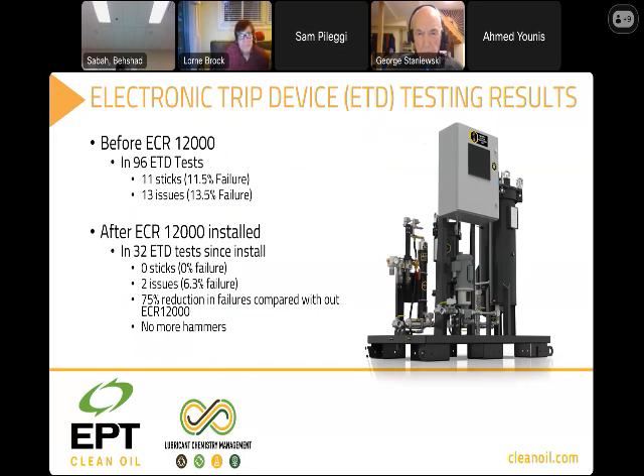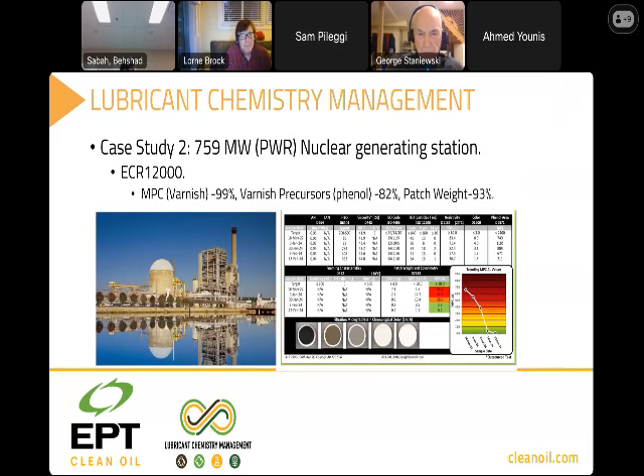The valve in 96 tests, they had about a 13% failure rate before. And after we put the system on, it went down to 6.3%. So pretty remarkable. Now, we don't see these results in the nuclear application because nuclear starting point is always really high, high quality, high sophistication. In the fossil burning plants, sometimes that sophistication isn't there, so you can see incredible improvements in mechanical performance.